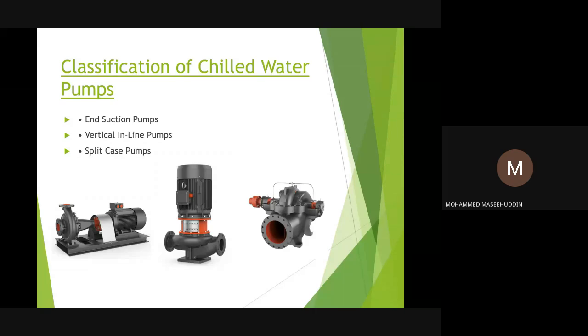This is the end suction pump, which is used mostly in the primary circuit of the chill water system. For you all, the primary circuit is the one which supplies the water from the tank up to the chiller, and it runs at constant speed, which in our case is mostly 4-pole, so 1450 rpm. The pump runs at constant speed because there is no variation in the pressure. It is just transferring the water from point A to point B. In this case, point A is the tank where the water is being held, and point B is the chiller.